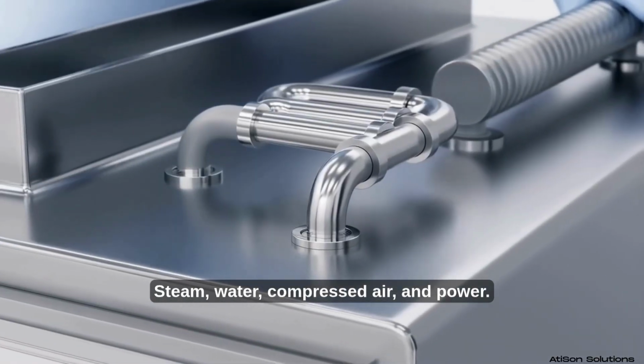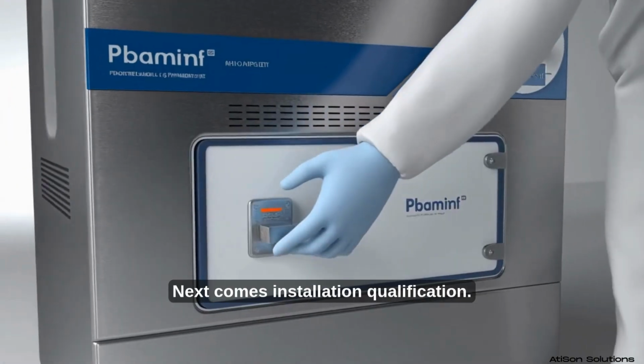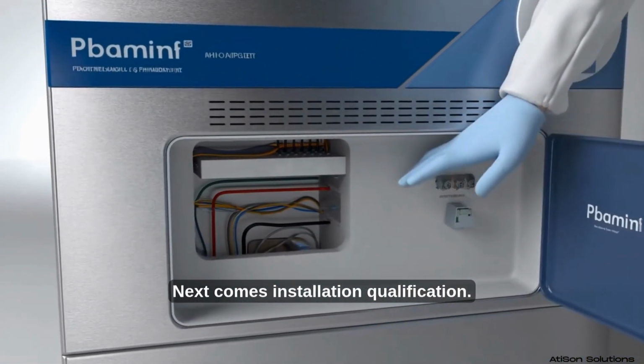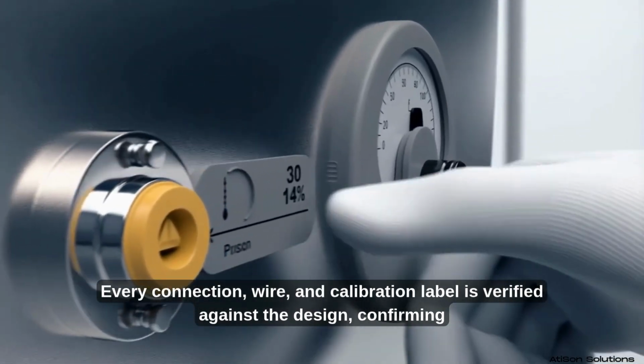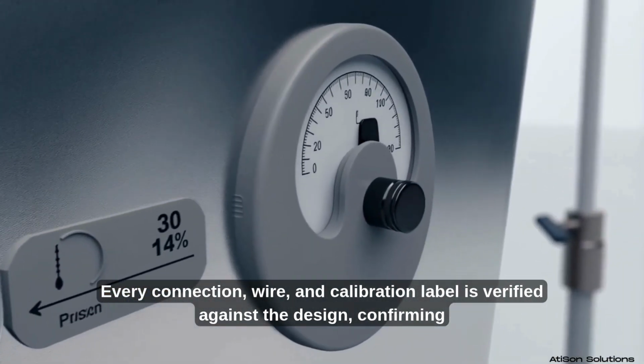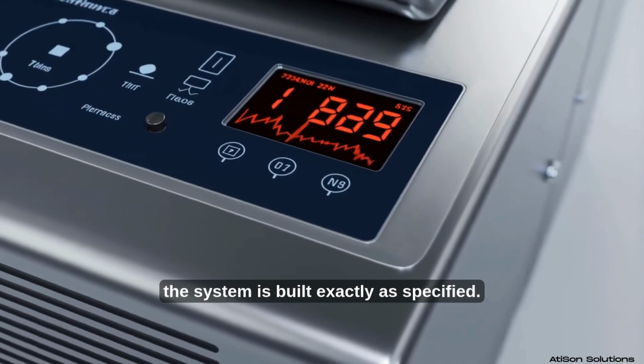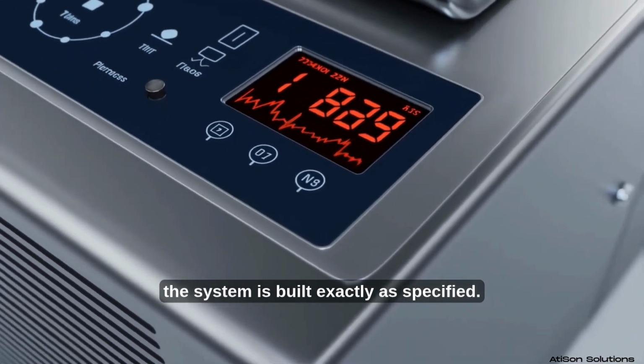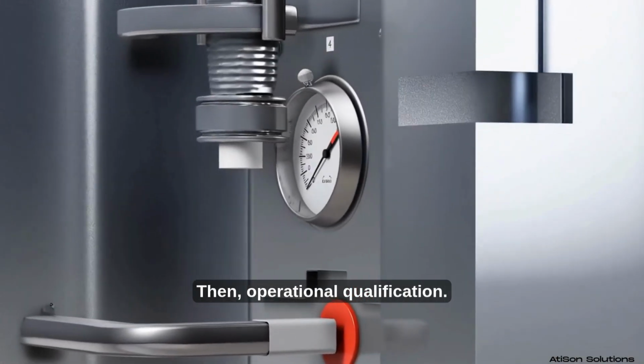Steam, water, compressed air, and power. Next comes installation qualification. Every connection, wire, and calibration label is verified against the design, confirming the system is built exactly as specified. Then, operational qualification.